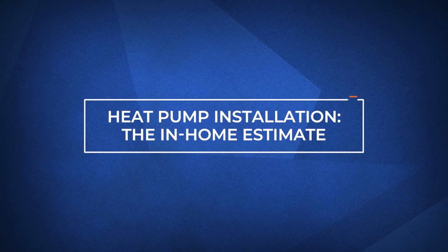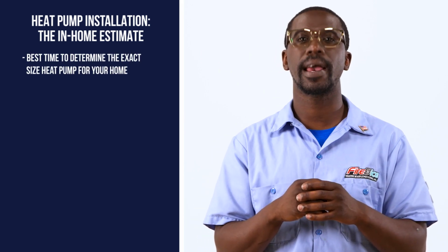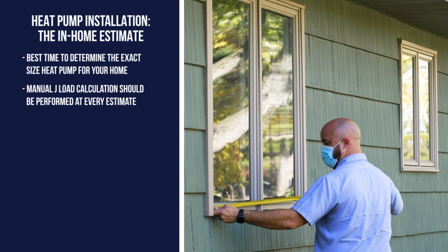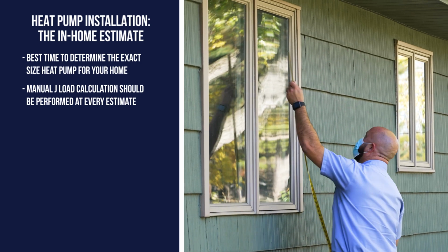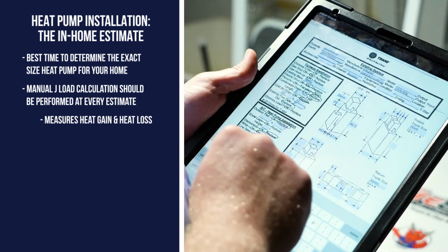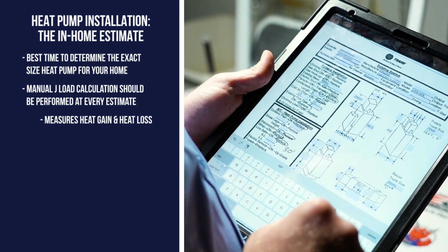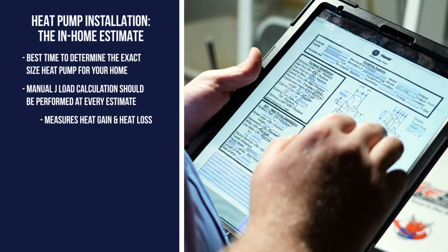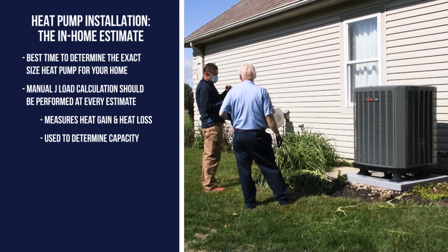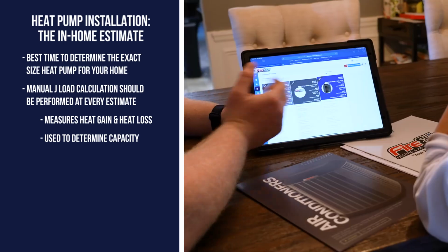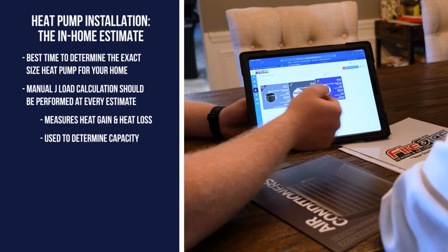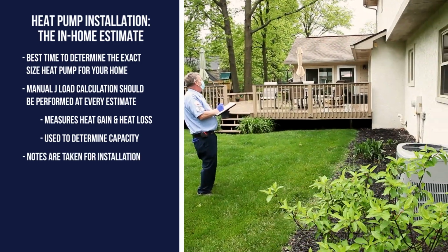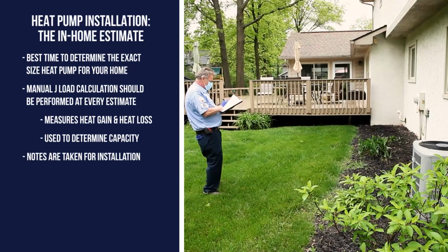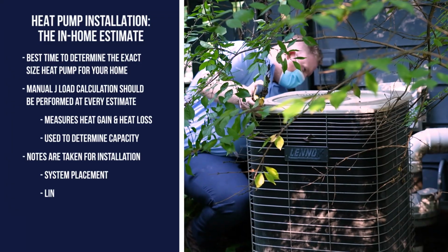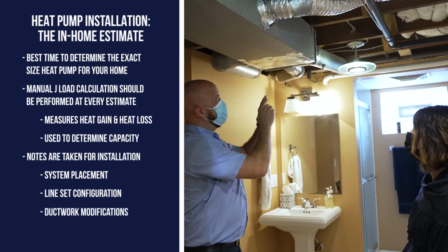Did you know all installations start with the in-home estimate? Why? Because it's the best time to determine the exact size heat pump for your home. To do this, a Manual J load calculation should be performed at every estimate. A load calculation is used to find how much heat your home naturally absorbs during the summer and releases during the winter. With a Manual J load calculation, you can determine the exact size heat pump that will meet your home's individual needs. Additionally, your sales professional will take note of any additional work that will be needed, such as the placement of your system, line set configuration, ductwork modifications, and more.